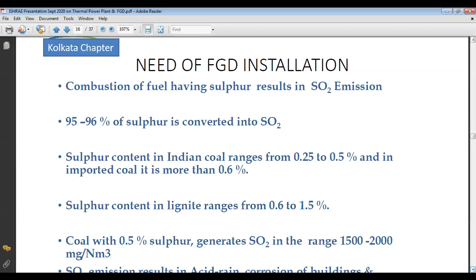Coal with 0.5% sulfur generates SO2 in the range of 1500 to 2000 milligrams per NM3. In the earlier slide we discussed that this limit was 600 for unit capacity less than 500 megawatt, and normally with 0.5% sulfur the SO2 is in the range of 1500 to 2000 milligrams per NM3. Even if the sulfur is around 0.25%, the SO2 will be in the range of 800 to 1000 milligrams per NM3. So to comply with this MOEF and CC norm, we have to install FGD technology.